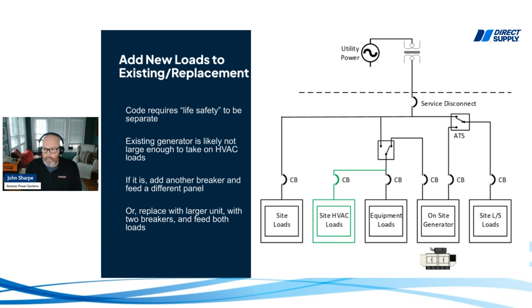But that's what you need to determine with the assessment: how much additional load am I putting on the equipment? What equipment do I have? Part of the assessment is how big of a generator do I have, and if I add these loads now, is this generator large enough to handle additional loads that weren't planned for on day one when it was installed?